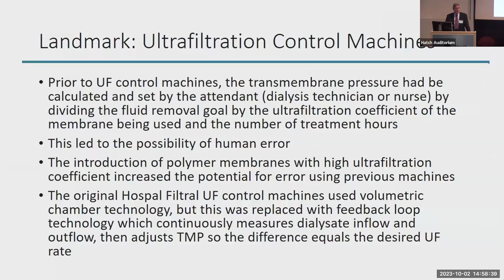And it usually worked, but again, there's human error that you're going to introduce into this process, which is probably not a great thing to do when a patient's life is at stake. So the polymer membranes with their high ultrafiltration coefficients mandated getting rid of this human component. The original ultrafiltration control machine for dialysis, as far as I remember, was the Hospal Filtral, which used a volumetric chamber technology, but this was ultimately replaced by the machines that we use today that use a feedback loop technology, which continuously measures the dialysate inflow and the dialysate outflow, the difference being the ultrafiltration rate, and then ultimately sets the ultrafiltration pressure to achieve the pre-programmed net ultrafiltration volume.